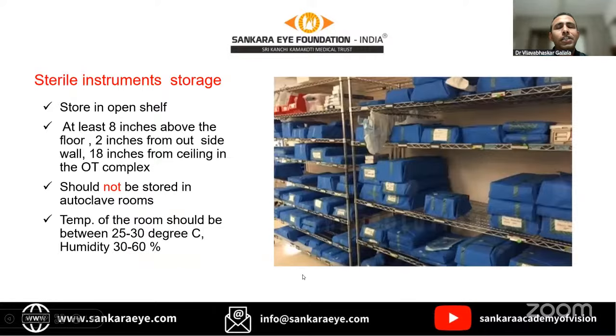And finally, once the sterilization process is over and everything is fine, we can store these instruments. For moist heat sterilization, you can store the instruments up to 48 hours. And ETO sterilized items can be used for up to 6 months. Always store them on an open shelf, not in a closed area. This shelf should be 8 inches above the floor, 2 inches away from the wall, and 18 inches from the ceiling. The items should not touch the floor, ceiling, or walls.